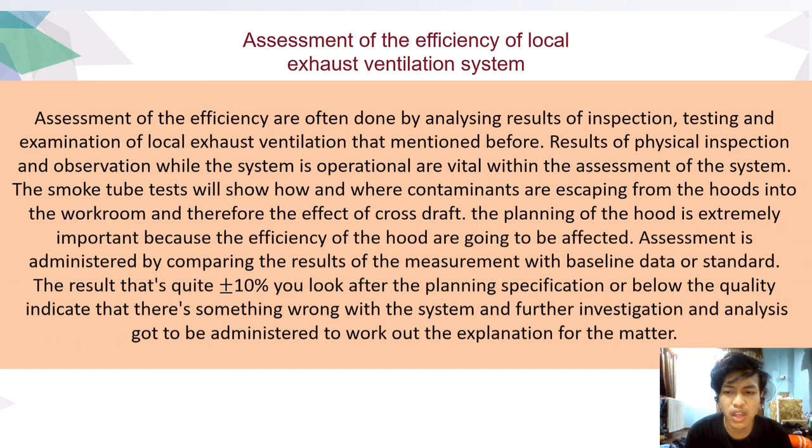The assessment is conducted by comparing the results of the measurement with baseline data and standard. The result required is within 10% of the design specification or below. Otherwise, it indicates that there is something wrong with the system, and further investigation and analysis need to be conducted to work out the reason for the problem. That's all for me.